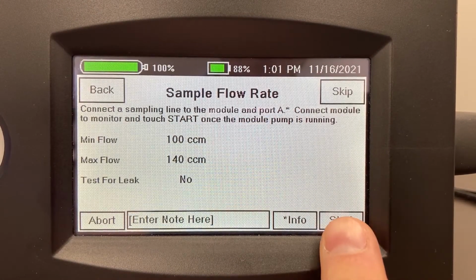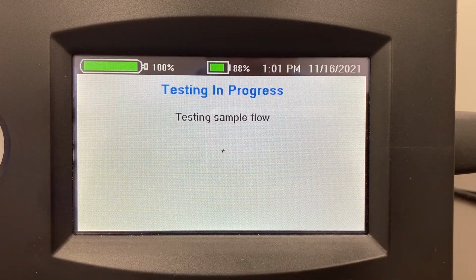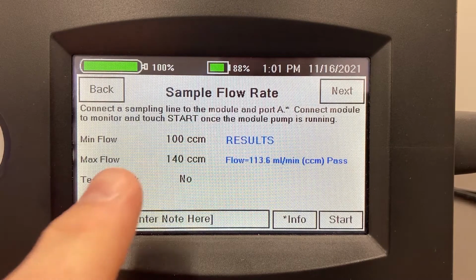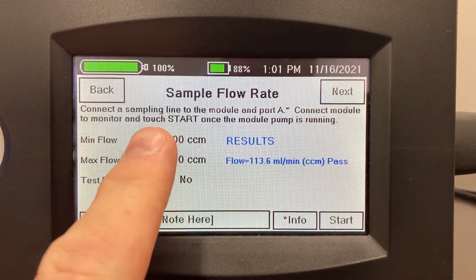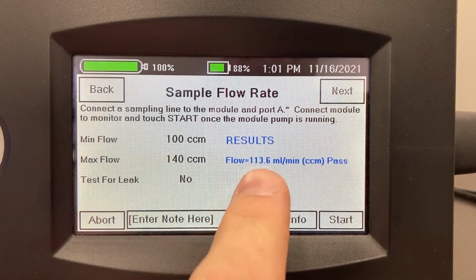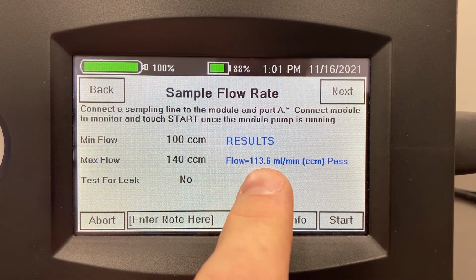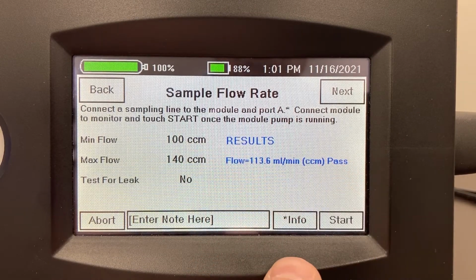Once the sample line is connected, we press start, and the SmartTank will measure the sample flow rate and return a value. You can see the pass criteria were between 100 and 140. The actual measured flow was 113.6, so this passed the test.